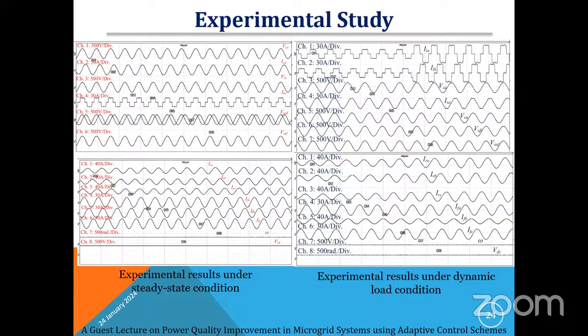The first case is the experimental result under steady-state condition. In the first figure we have source voltage and source current. If you see here, the DC offset is completely zero. The voltage magnitude is also maintaining zero offset, and harmonics are very low in this steady-state condition. These are the load currents, and these are the internal characteristics of the alpha-beta components of the MCCF. The MCCF internal characteristics we have also calculated in real time. This is the fundamental component of the voltage, that is the MCCF controller's output. These are the control characteristics: reference voltages A, B, C, and the compensating currents. After giving the PWM pulses to the voltage source inverter, the inverter develops these three currents for harmonic elimination in the system.